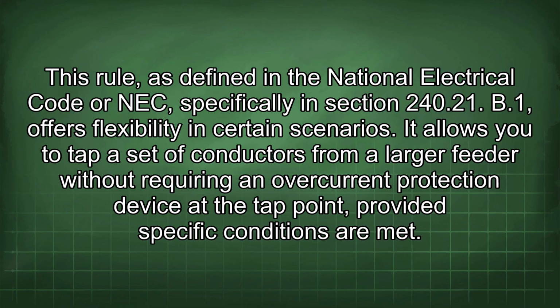This rule, as defined in the National Electrical Code or NEC, specifically in section 240.21(B)(1), offers flexibility in certain scenarios. It allows you to tap a set of conductors from a larger feeder without requiring an overcurrent protection device at the tap point, provided specific conditions are met.